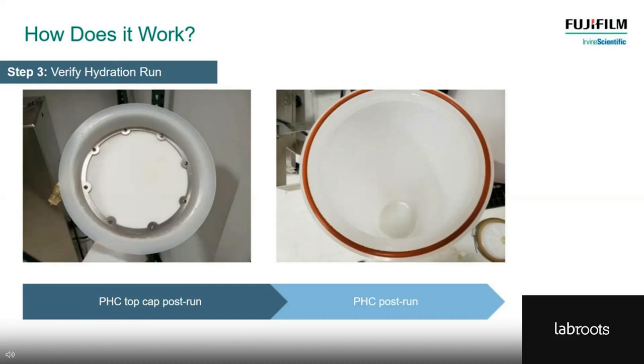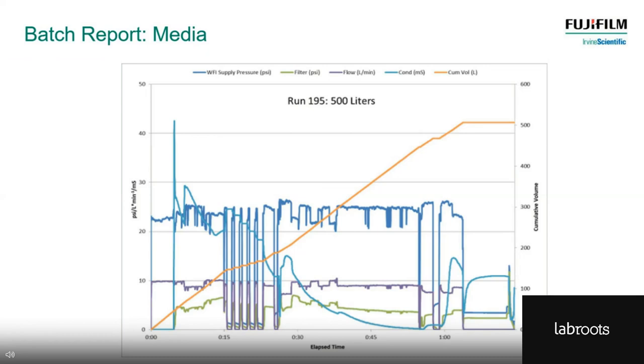One of the things we do as we run the development process is inspect the inside of the media cartridge after a run — looking at the coarse filter at the top of the cartridge that protects the sterilizing-grade filter, and looking down at the base to make sure there are no powder residues. On the skid itself, there are a number of sensors monitoring and controlling the process, which produces a dataset. The orange line is the total volume. The darker blue line across the middle is the water supply pressure. The light blue line is conductivity, spiking at the beginning and gradually dropping down to zero.